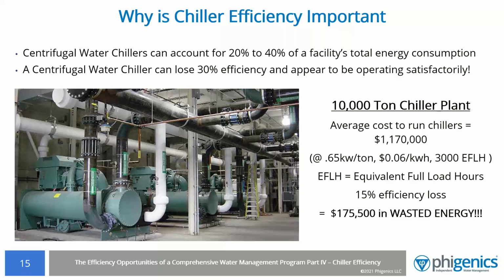Why is chiller efficiency important? Well, did you know that centrifugal water chillers can account for 20 to 40% of a facility's total energy consumption? Or that it can lose 30% efficiency and appear to be operating satisfactorily? This is an example of a typical chiller plant in a large building or small college campus complex. The assumptions are that the plant is running at an efficiency of .65 kilowatts per ton, the cost of electricity is 6 cents per kilowatt, and that the equivalent full load cooling hours is 3,000.